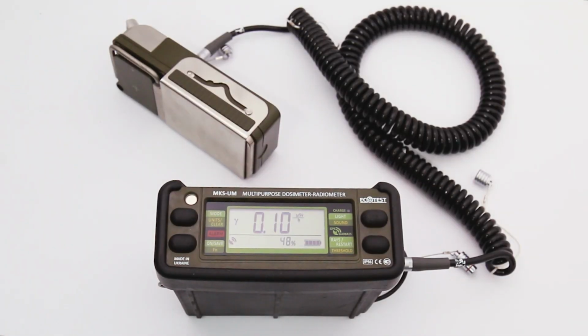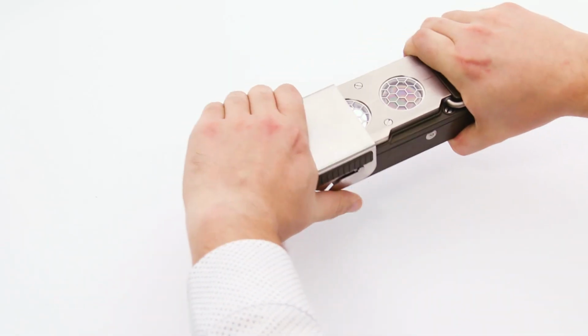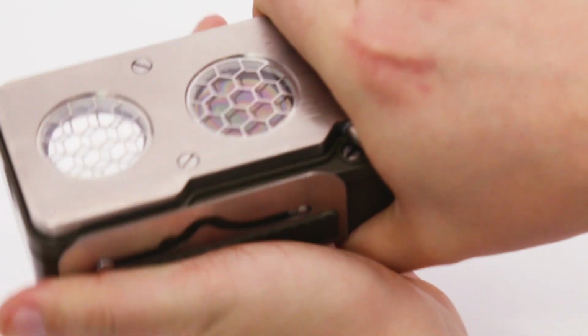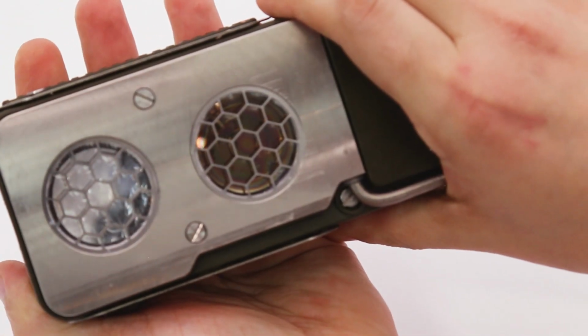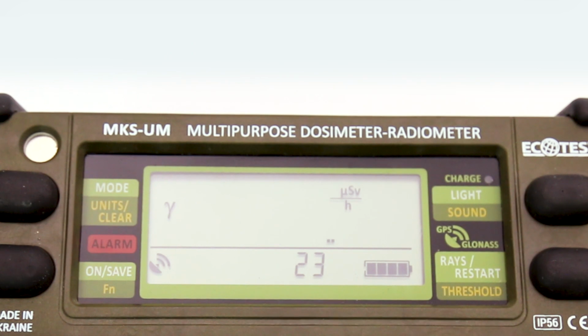When conducting measurements of the dose rate using the BDKS-02 detecting probe, the alpha radiation is also monitored. In this case, the alpha detector window must be kept open. The flashing alpha symbol, sound and light alarms indicate the alpha radiation is present.